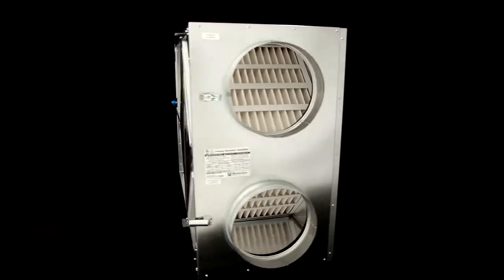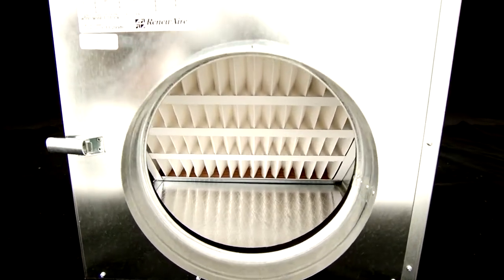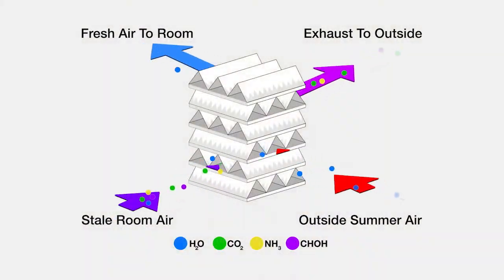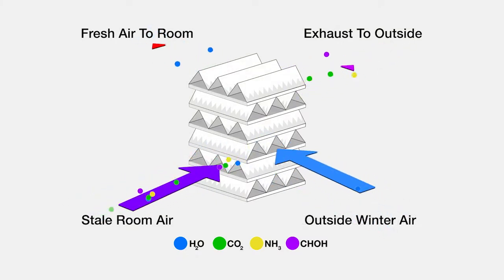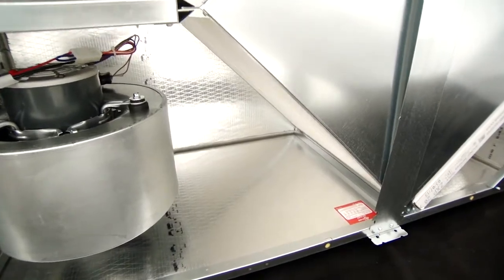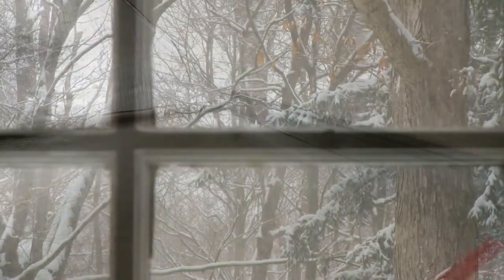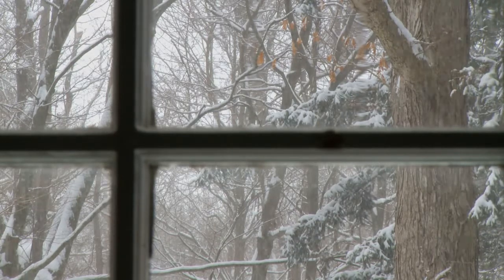Compare Renew Air to other ERV systems and you'll see important advantages. Renew Air's superior performance starts with our remarkable static plate core. Hygroscopic resin plates transfer temperature and humidity with zero actual air and pollution transfer, and they do it passively — without the rotating wheels or chemical desiccants used by others. Since the Renew Air core operates dry, there is no need for condensate pans and drains, and in cold climates the need for defrost is eliminated except in the most extreme environments.